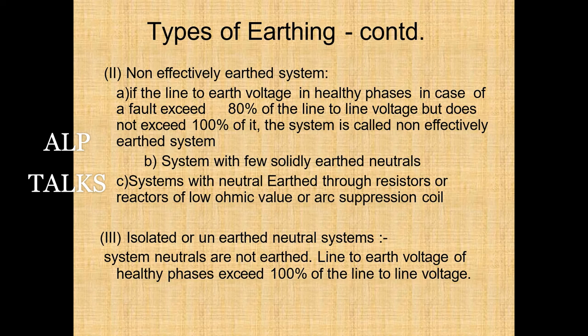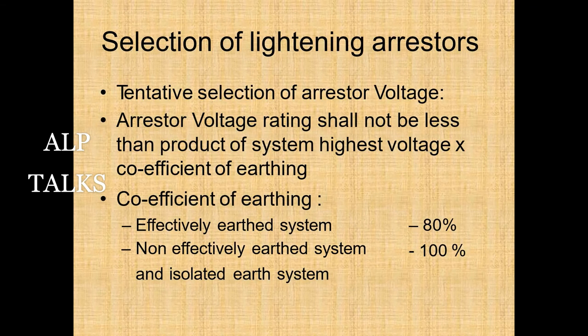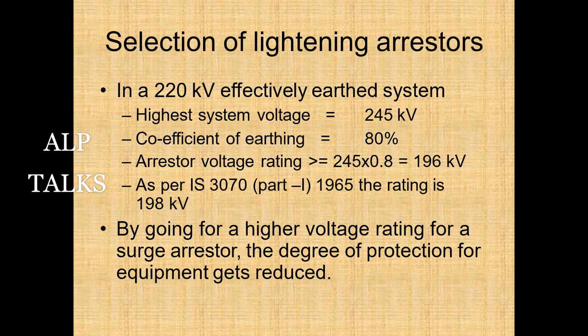Tentative arrester selection: arrester voltage rating shall not be less than the product of the highest system voltage and the coefficient of earthing — 80% for effectively earthed systems and 100% for non-effectively earthed and isolated earthed systems. For example, in a 220 kV effectively earthed system with highest voltage of 245 kV: 245 × 0.8 = 196 kV, so a standard rating of 198 kV is selected. However, by going for a higher voltage rating for a surge arrester, the degree of protection offered to the equipment is reduced.